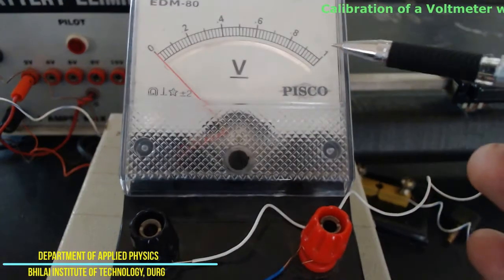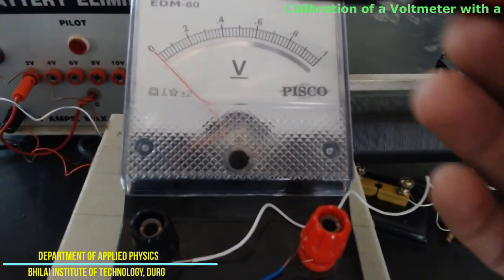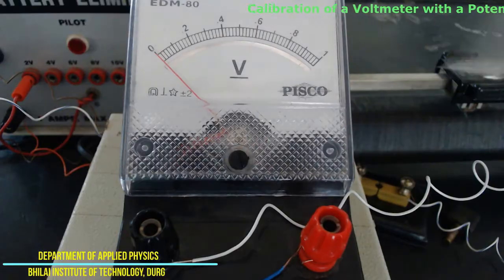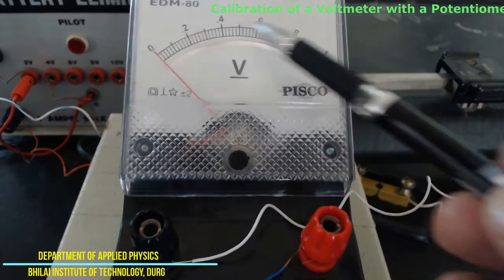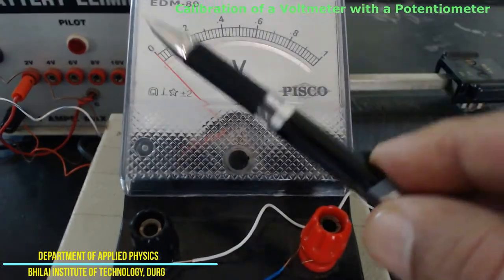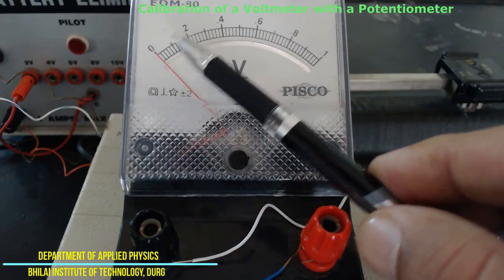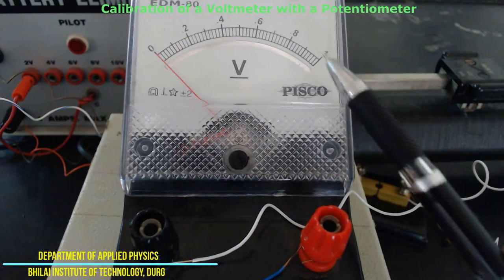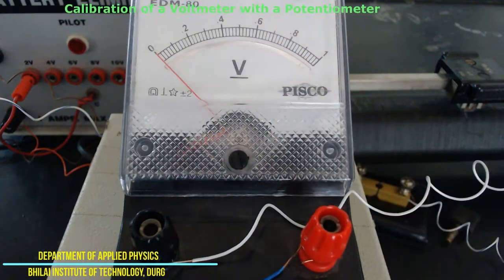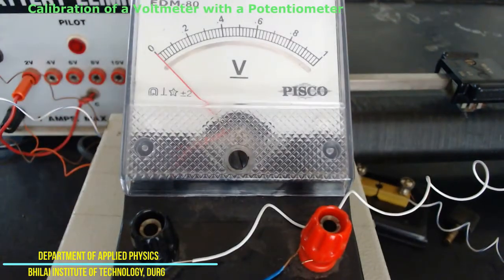This is the 1 volt mark, 0.8, 0.6, 0.4, 0.2 and 0. So this is to be calibrated for the complete range, which means we have to take the readings of 0.1, 0.2, 0.3 up to 1 volt. The complete range is always calibrated. So this is the voltmeter which is to be calibrated.